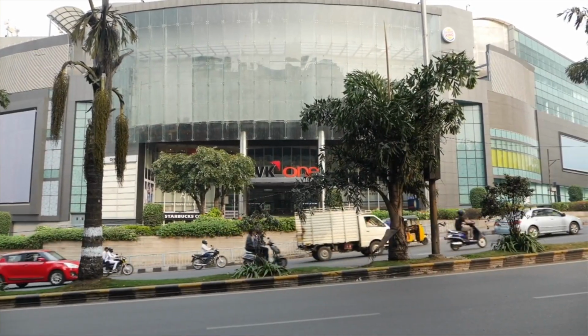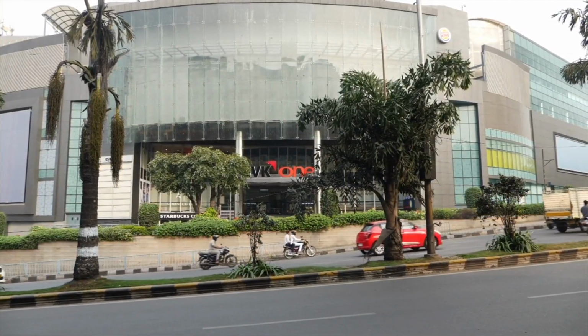Building a charge point involves proper planning - sufficient real estate and a power source are required. For the power source, say a Bescom connection here in Bangalore or Karnataka, Bescom will sanction a certain load, and depending on the loading requirement, they decide at what voltage the service should be given. For any charging station up to 150 kilowatt, they provide LT supply, low tension supply, with a dedicated transformer. With these minimum requirements - a dedicated transformer - any charging station can be started.